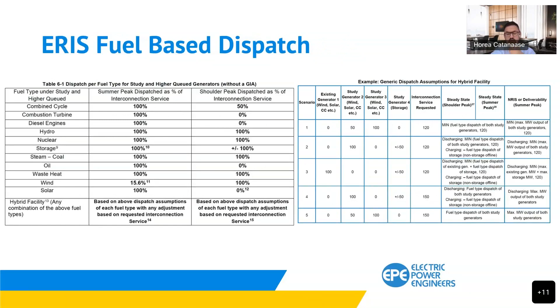We've looked at different dispatch methodologies and how they are applied across two major RTOs. It's important to note that the ramping and sinking of generators under study is not based on an economic dispatch model, and this may lead to a few questions. For example, in flow gate screening, what is the probability that the top 30 worst contributors to constraint are all online, plus all the study generators at the same time? Could this potentially lead to expensive upgrades?